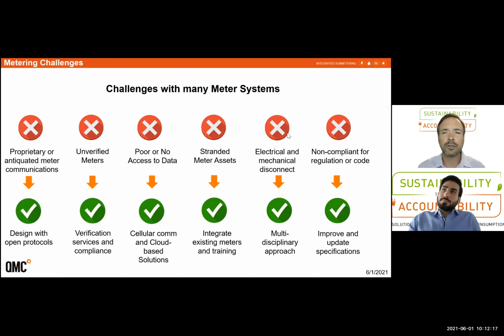There's historically been a disconnect between electrical and mechanical systems being deployed. One thing that happens is a lot of electrical metering was being put into buildings and very few gas or water or thermal meters. So that imbalances the problem, but also those systems often operate on completely different control systems or data collection systems. So you have to go to one system to get the electrical metering, another to get the gas, another to get the water, and maybe even a fourth to get the BTU metering data. And so we really try to encourage all the parties we work with to align the electrical and mechanical systems into one meter system.